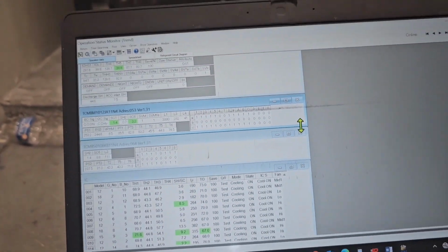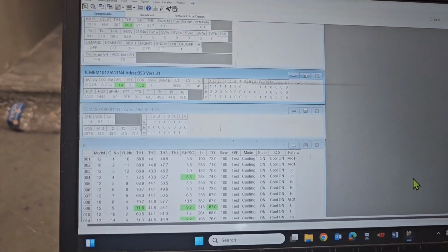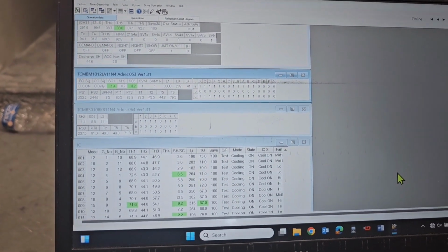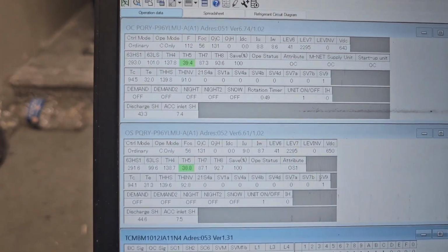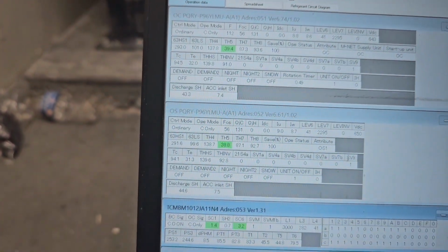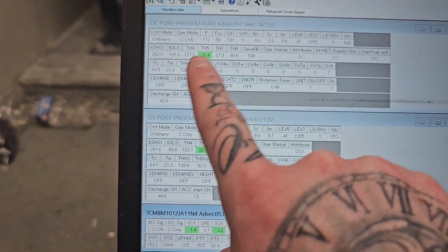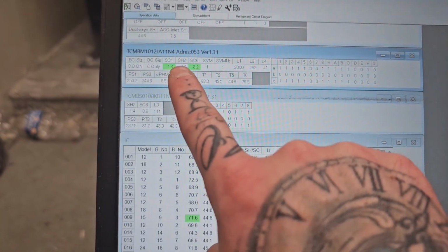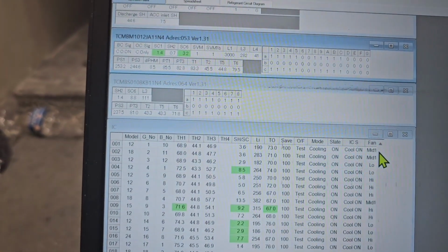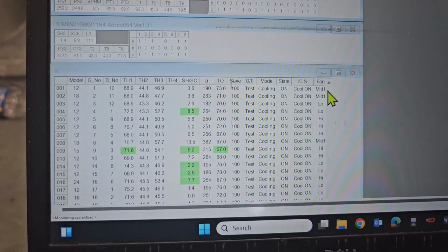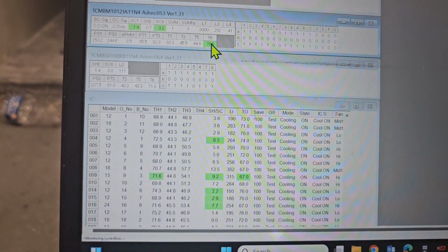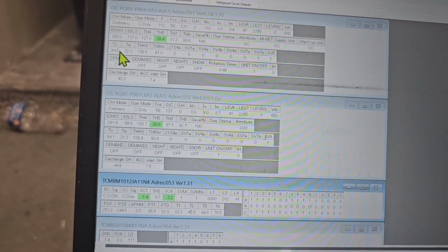This is why you have to watch it for a long time, because one slide doesn't tell you anything. One slide is 1 minute of data, and it can be completely different 60 seconds later. And if we go back here, you can see what I was saying about there should be superheat there. So right now, we've got about 8 degrees of superheat at our outdoor unit. No superheat there. Light subcooling, but I think it's just because these units are water source, so they don't need as much subcooling. You can see our T6, our liquid line going to our indoor units, is about 80 degrees. Condensing temp is 95, so we've got about 15 degrees of subcooling anyway.